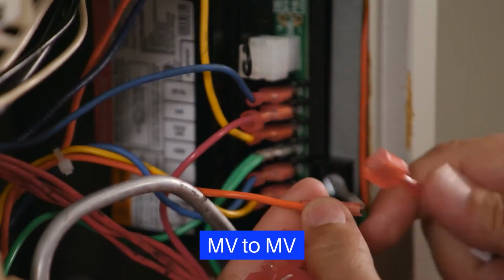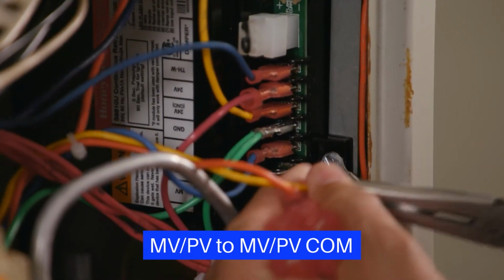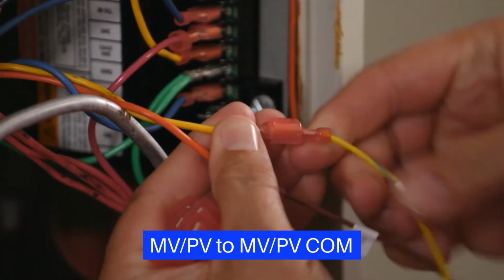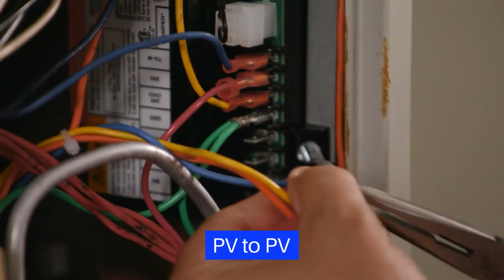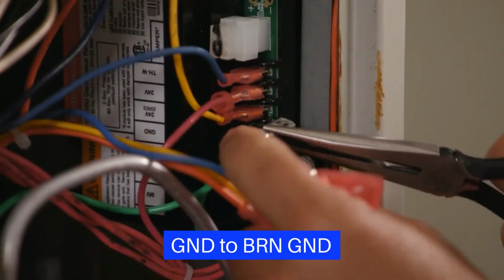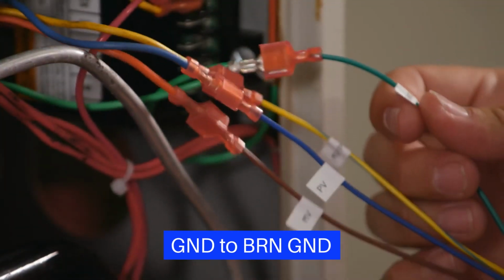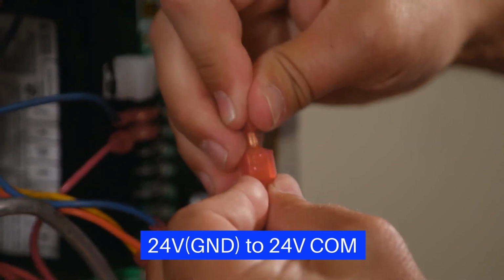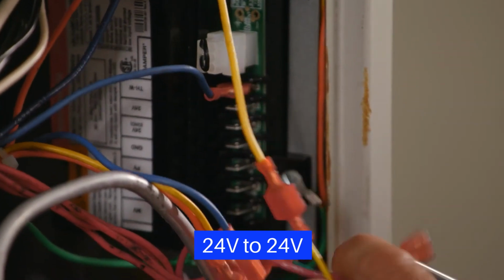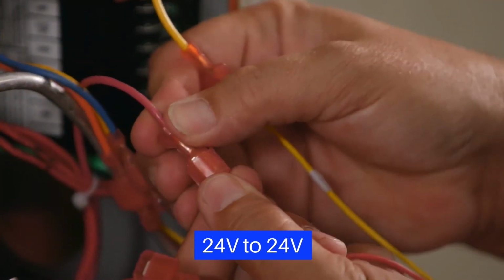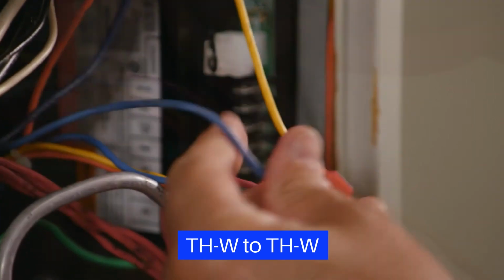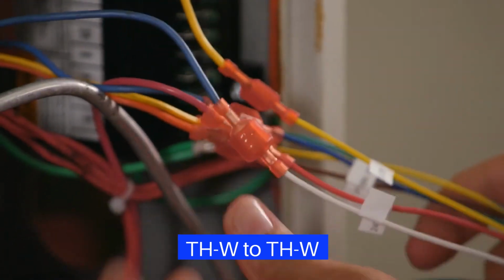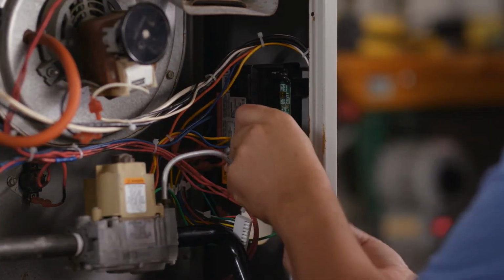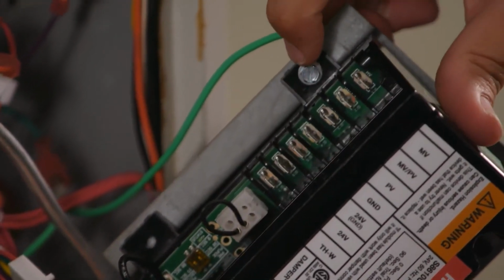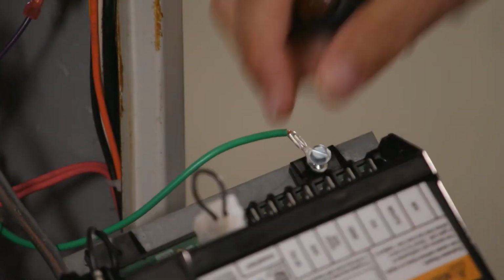Connect the MV to MV, MV-PV to MV-PV-COM, PV to PV, GND to BRN-GND, 24-volt GND to 24-volt COM, 24-volt to 24-volt, and finally THW to THW. Once all wires have been transferred, remove the existing module. Take note if there is a ground wire attached to one of the mounting screws.